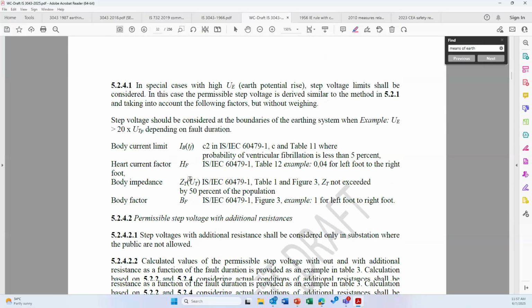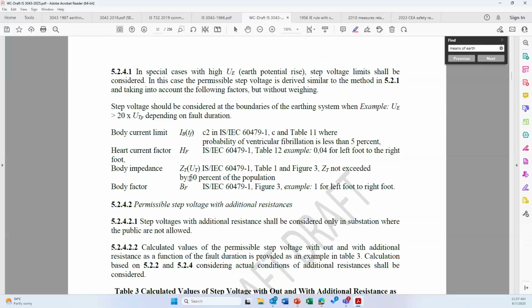Similarly, for step voltage, the body factor, the heart factor is considered as in the case of a touch voltage. When you touch an exposed conductive part, a faulty conductive part, or a touch potential with your left hand, the heart factor considering a current flow through the left hand to the feet is considered as heart factor 1, and the heart factor considered is 0.04 for step potential. So these are some of the information which is included.